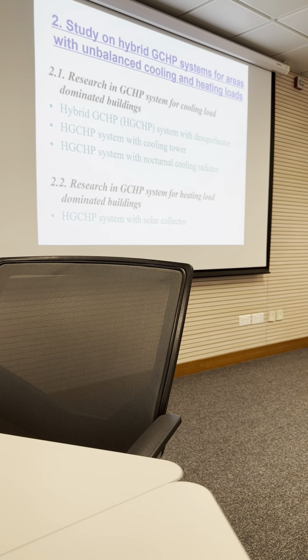Then if we use a ground coupled heat pump system, we only extract energy from the ground. But we don't need to extract energy from the ground all year, because in summer they don't need heating, but they don't need cooling as well. Then the temperature of the ground gradually recovers. So we did some research in this area. For example, for a cooling load dominant building, can we use the system to produce hot water at the same time? We don't want to solve the problem for all kinds of buildings. But in hospitals and hotels, we need hot water. Residential buildings need hot water nearly every day throughout the year for washing and taking showers.